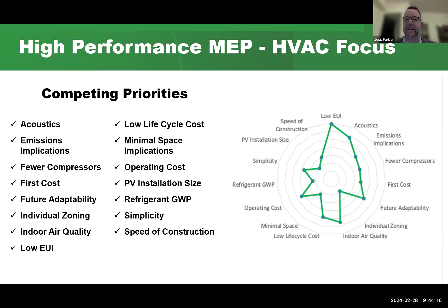We did what's called a distributed geothermal HVAC system. As Mike mentioned earlier, we have ground source wells out in the parking lot—60 of them, 500 feet deep—that go back into the building into a water loop connected to individual heat pumps around the building that handle the individual heating and cooling throughout. This same unit heats and cools—you're buying one system to do 2 jobs, which is important compared to separate chillers and boilers, which are 2 separate systems you'd buy. This is one system that does both jobs.